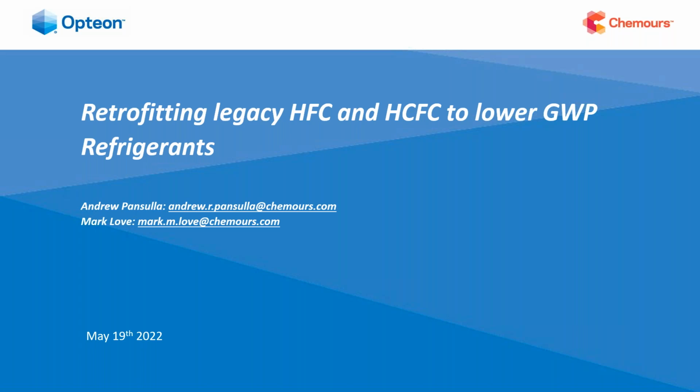That's a good question. So if you look at the components of 449A, 449A is a 4-component blend. It's got 32, 125, 134A, and 1234YF in the blend. And then 448A is a 5-component blend. So it has the 4 components of 449A, and in addition to that, it has 7% 1234ZE in it. Quite honestly, much like I've talked about the two interchangeably in the presentation, you're not going to see a large performance difference between the two gases. So there's really not all that much of a difference beyond 448A is dependent on a ZE supply in addition to the other components.